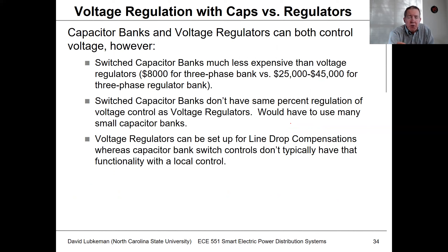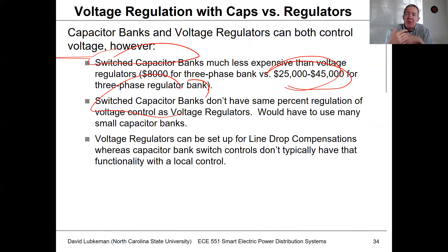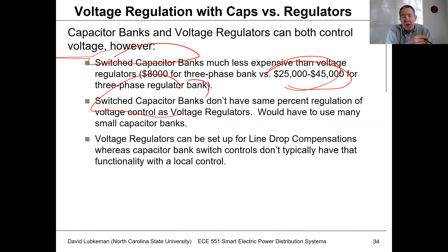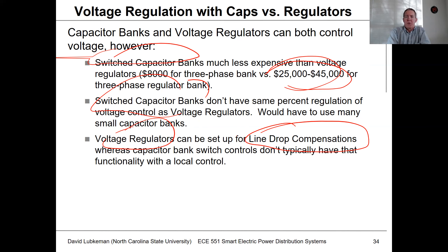To compare: switched capacitor banks are much less expensive as an investment, while three-phase regulators are considerably more expensive. The problem with switched capacitor banks is you have to switch in large increments — typically 1200, 1800, or 2100 k-var at a time — so the voltage jumps significantly up or down. Line regulators allow fine-tuned adjustments and provide additional functionality through current measurements enabling line drop compensation. If you need more exact control, you'd have to go with the line voltage regulator, but if you just want an overall boost in voltage, capacitors would be the way to go.